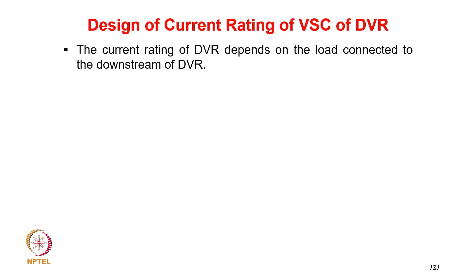Now coming to design of current rating of VSC. The current rating of DVR depends upon the load connected downstream of the DVR. So for a 20 kVA load, the current is calculated as root 3 VL into IL equal to 20,000, from which we get IL equal to 27.82, and the current rating of DVR will be 27.82 ampere.